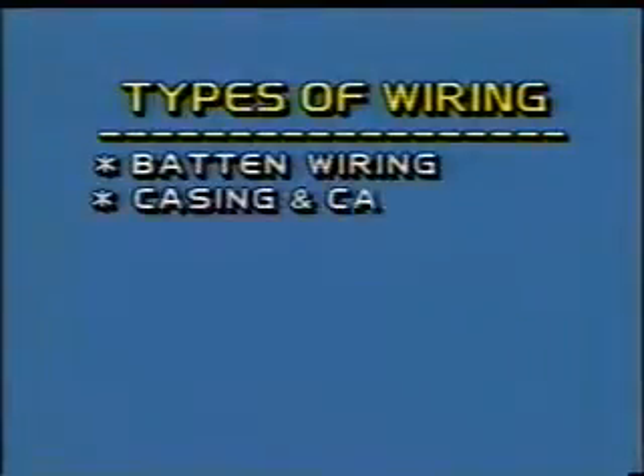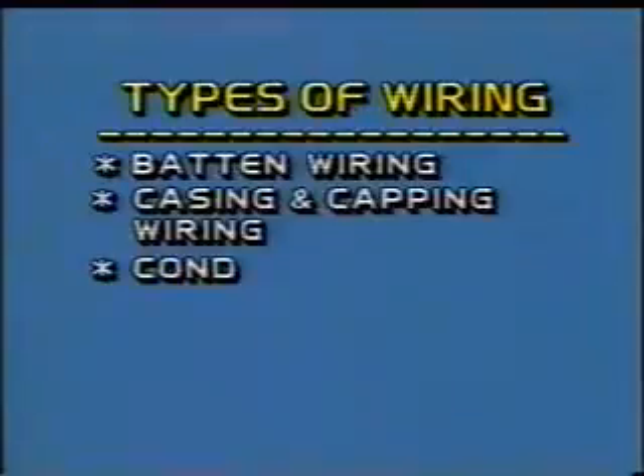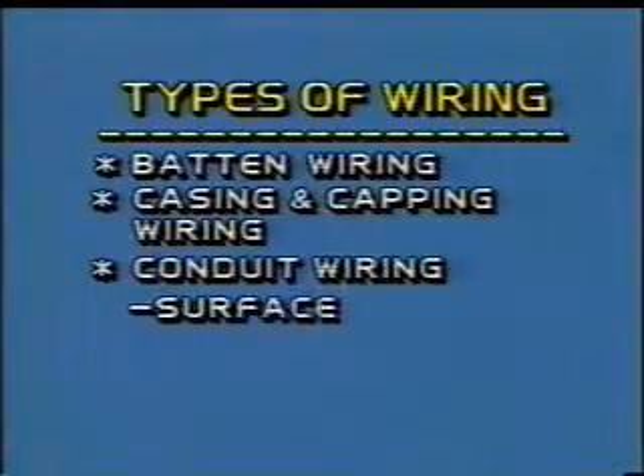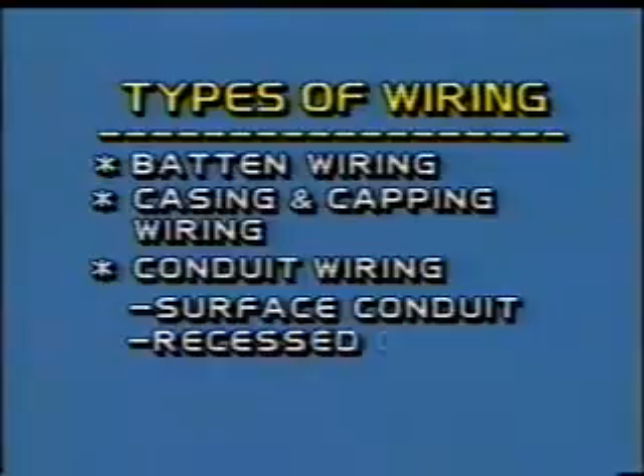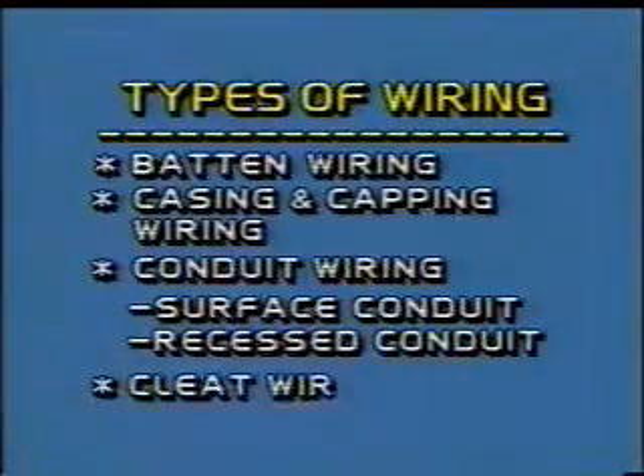The wiring of light and fan circuits as well as the power circuits can be done in different ways. Thus we have the following types of wiring systems: batten wiring, casing and capping, conduit wiring, that is surface conduit wiring or recessed conduit wiring, and cleat wiring. The batten wiring is very simple and economical.